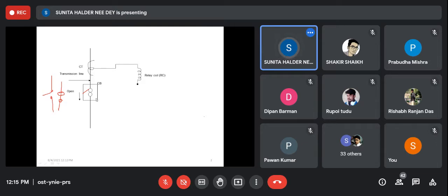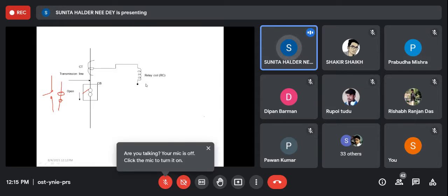So if it is a very sensitive line, then for the transmission line, the three phase fault is the most severe fault. So you may set the relay coil setting for that most severe fault, or the least severe fault. I think it is the single phase to ground fault. Maybe I have forgotten the expression. Anyway, you can set for that one also. So the importance you give in this protection scheme, the setting will depend on that.